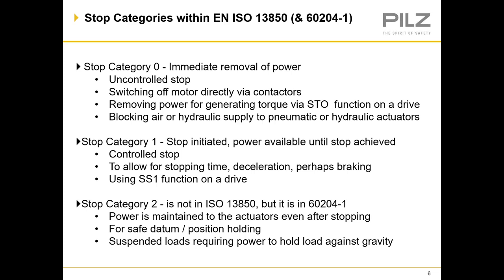Stop category 1: stop initiated, power available until stop is achieved — this is a controlled stop. This allows for machine stopping times, time delay stops, deceleration and braking used with control systems to indicate machinery is stationary. It may be used for fast moving machinery to protect the machine. It could have instant operational contacts along with time delay contacts, and it's achieved using the SS1 function on a variable speed drive.